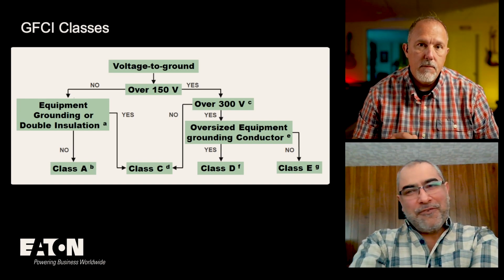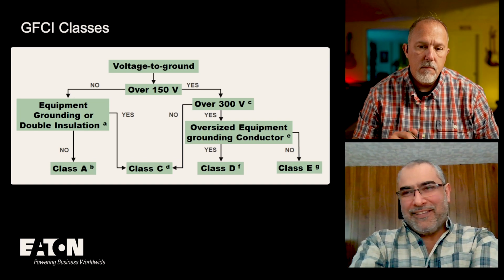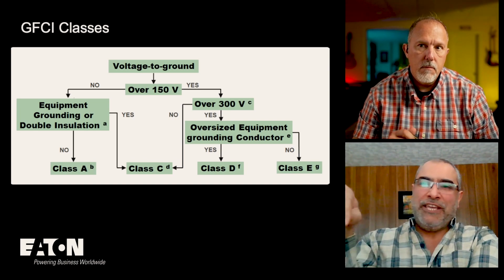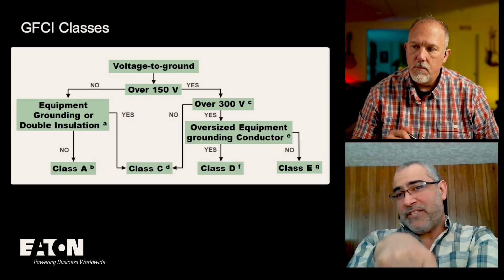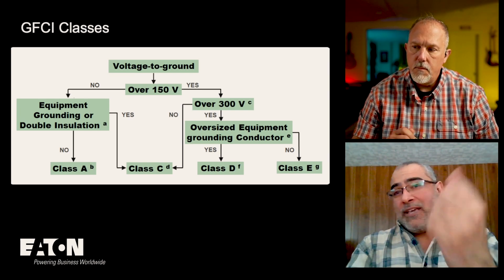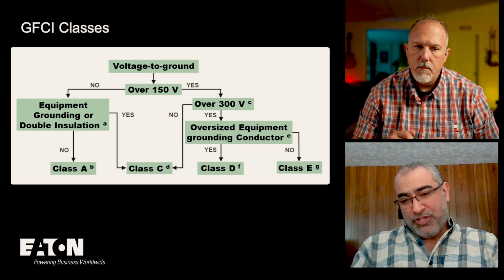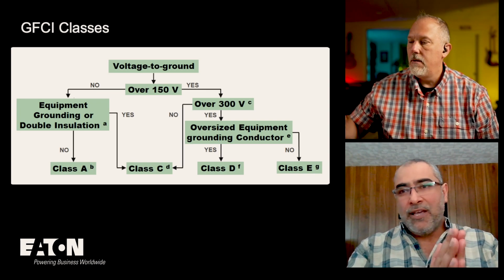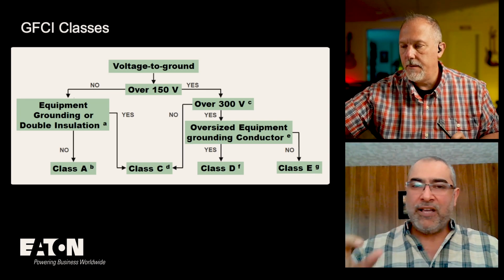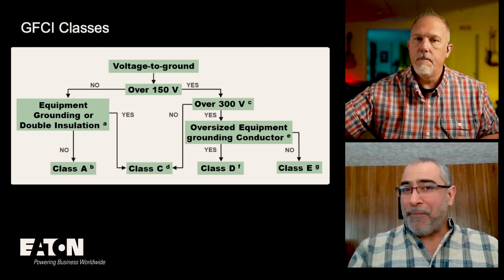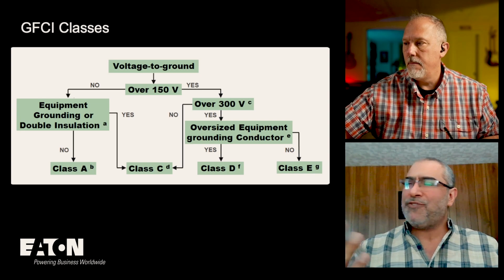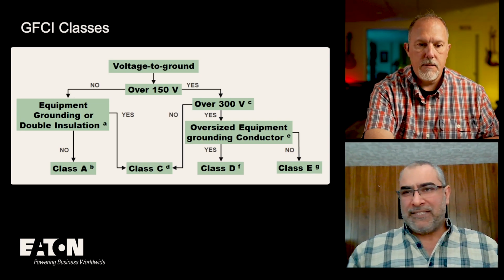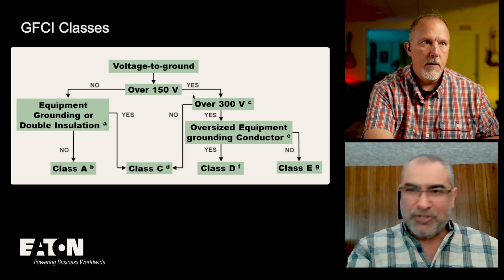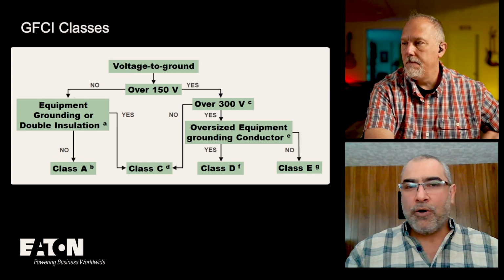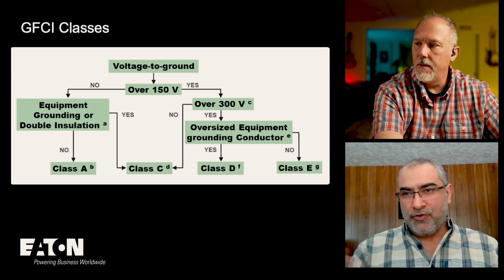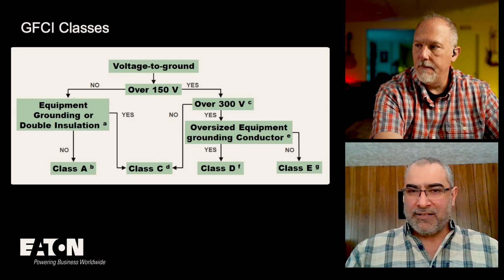I'm laughing because I think we discussed this during the first draft meeting, and this is one of my public comments. Remember, Tom, we made a change in the first draft in the definition of special purpose GFCIs. There's no such thing as a special purpose GFCI definition. If you check 943C, this outline of investigation, it does not define special purpose GFCI. What it defines is Class C, Class D, Class E. My public comment, once the public comment stage opens, will be to get rid of the special purpose GFCI definition and call a spade a spade: Class A GFCI, Class C, Class D, Class E.